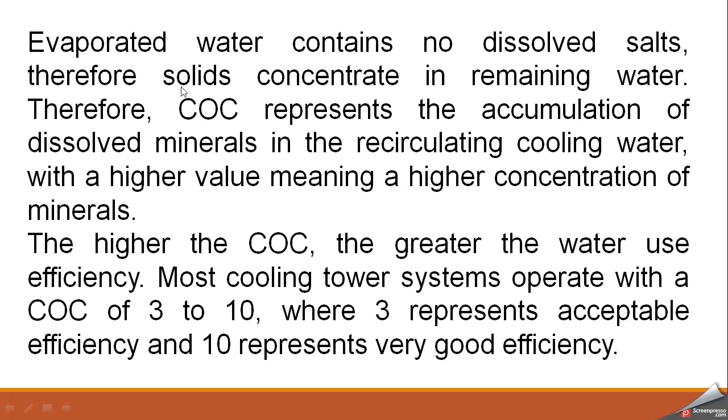Normally what happens during the cooling tower operation? The evaporated water contains no dissolved solids. It is the pure form of water and it cannot carry any of the dissolved solids. Therefore solids concentrate in the remaining water, because when some of the water evaporates, the remaining water is much more concentrated in the minerals present in it, since the evaporated water does not take any of the minerals with it.